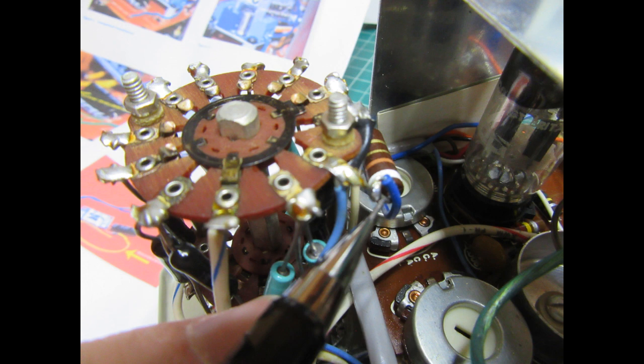Those should be nice and shiny, and it's imperative that you get these working well, because if you're making bad connections on these switches, then you're not going to get good results from the meter. It's not going to work properly. And for this, I just use regular DeoxIT products. There's several different kinds, but their most common product, I think it's called D5. Or you can use any of the other brands of switch DeoxIT products.